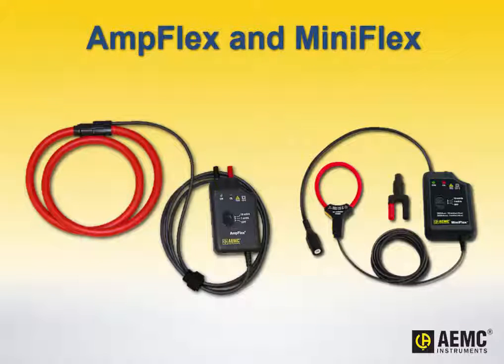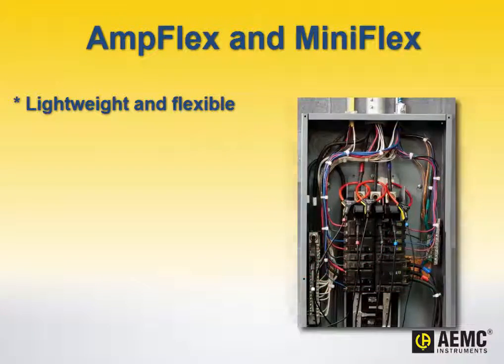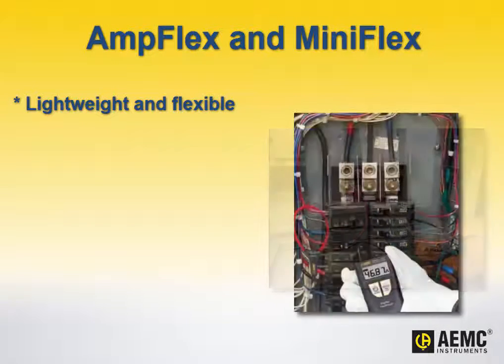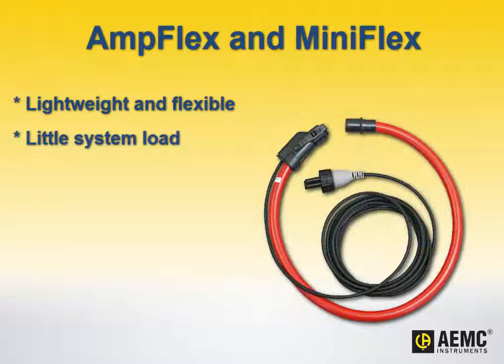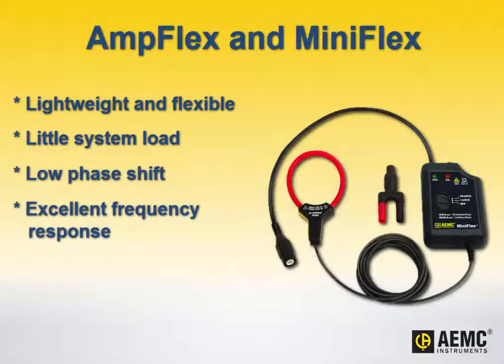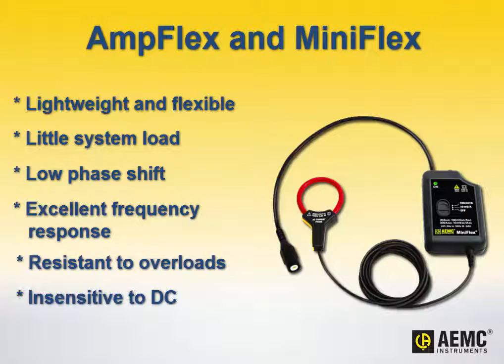The AEMC AmpFlex and MiniFlex families of AC current probes enable measurements on conductors where standard clamp-on probes cannot be used. AmFlex and Miniflex probes are lightweight and can be installed in tight places, around cable bundles, around wide or large bus bars, or even wrapped around irregular shapes. These probes create virtually no load on the system under test, have a low phase shift and excellent frequency response, and cannot be damaged by overloads, and they are insensitive to DC currents, so only the AC component of the measured signal is displayed.